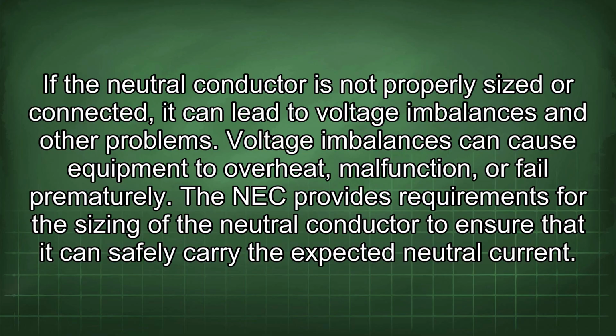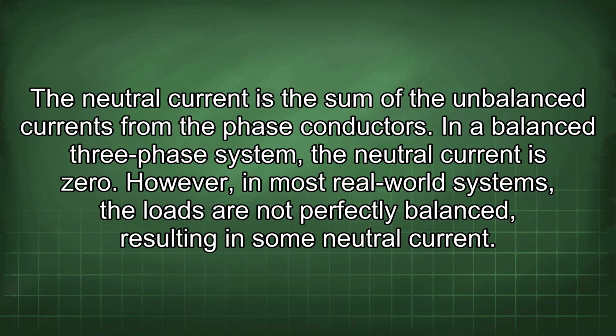The NEC provides requirements for the sizing of the neutral conductor to ensure that it can safely carry the expected neutral current. The neutral current is the sum of the unbalanced currents from the phase conductors. In a balanced three-phase system, the neutral current is zero. However, in most real-world systems, the loads are not perfectly balanced, resulting in some neutral current.